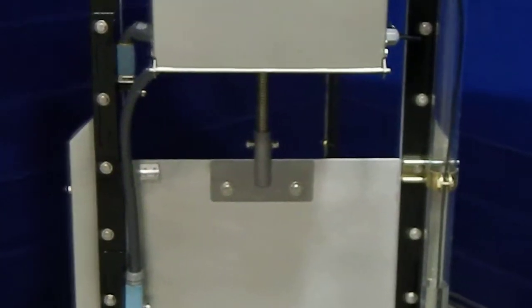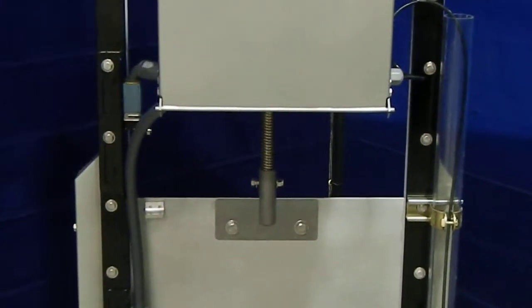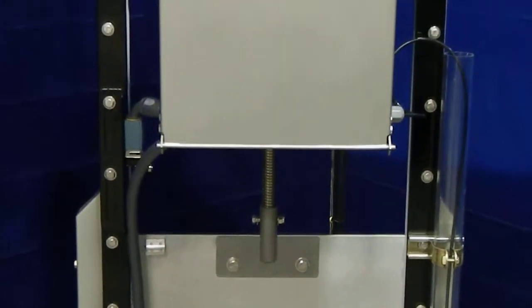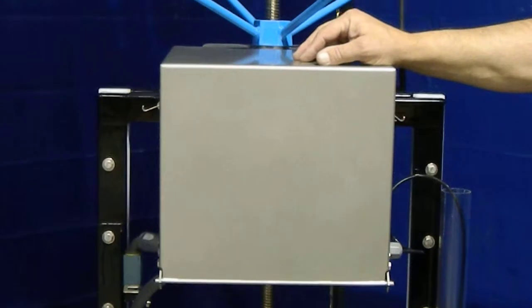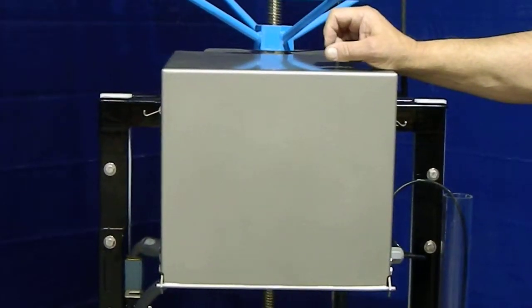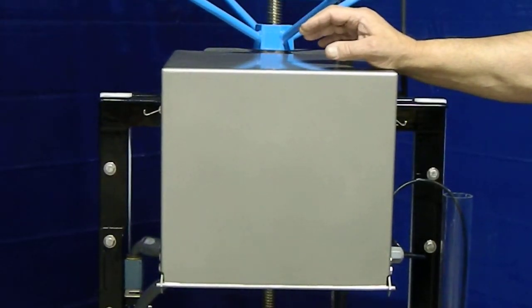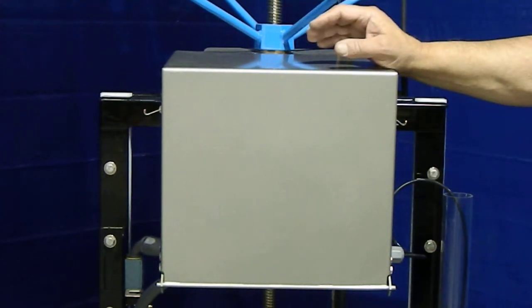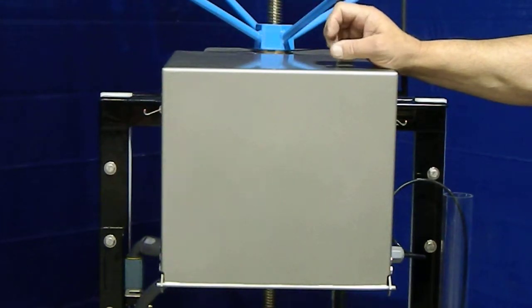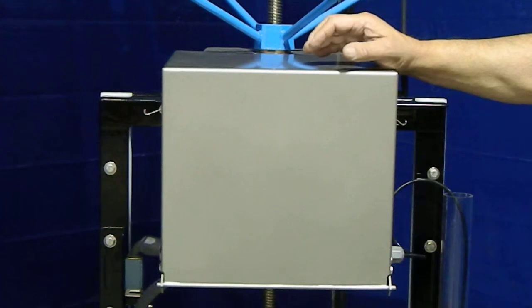It also shows up on the screen, so you know you've hit your hard limit. Now, the difference between a hard limit and a soft limit is the soft limit is set in software. The hard limit is set in hardware, so that if for any reason the software fails, you have a hardware backup. We at Watch Technologies always want to make sure that something's going to work.